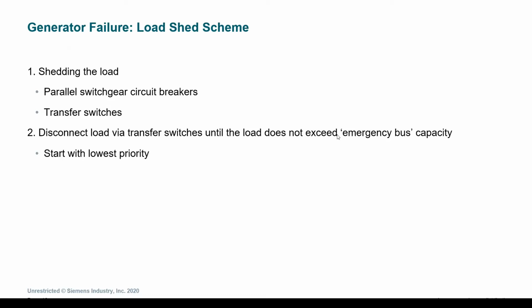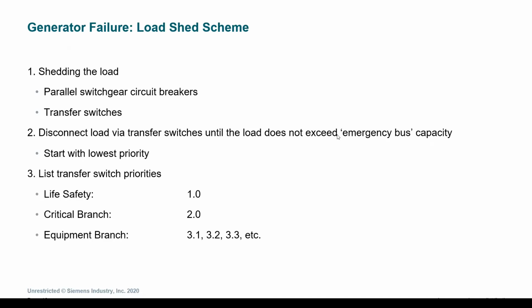Again, although similar to what Jeremy mentioned on being very unlikely, similar to the load shed, we want to make sure the system is programmed to operate in any condition, no matter how many failures happen, to ensure the most potential operation of the facility can be done. So to begin this process, we want to list off each of the transfer switches by priority. Life safety, obviously first, critical, second, and equipment branch, designating a separate priority for each of those transfer switches.